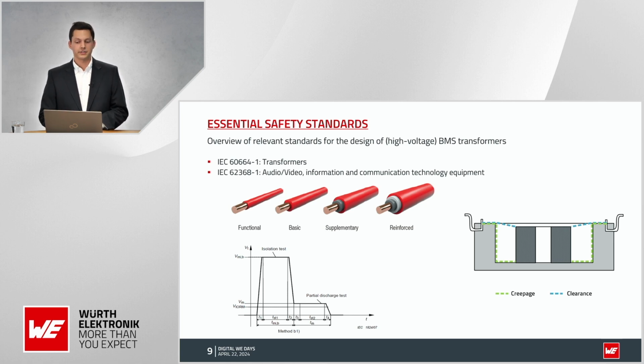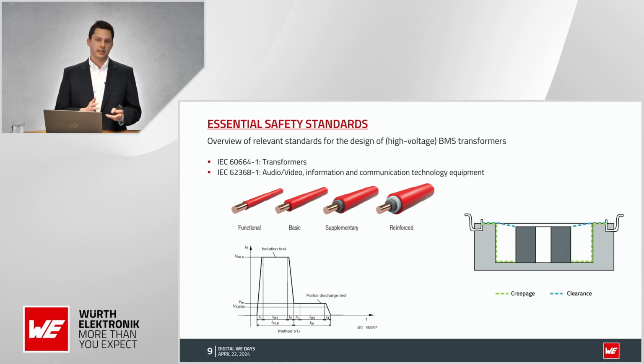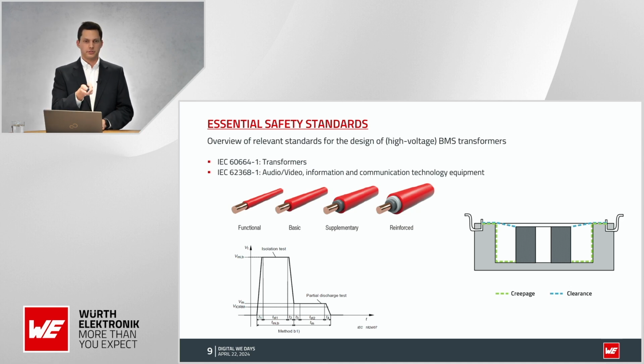Important aspects in designing of a BMS transformer according to these norms are the creepage and clearance distances, as well as the selection of a suitable insulation for the wire. A distinction is made between functional, basic, supplementary and reinforced isolation. The different types of isolations can be seen in the left upper picture, so as you can see in here. Functional isolation is the minimum level requirement for functionality. However, this type of isolation does not prevent electrical shock.